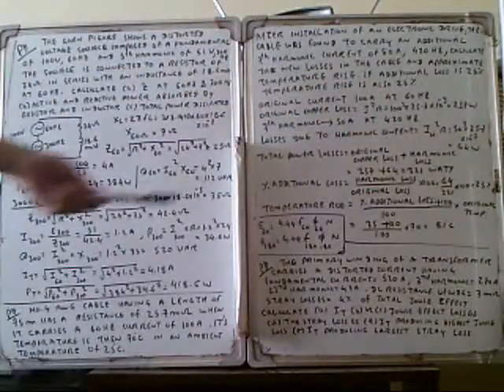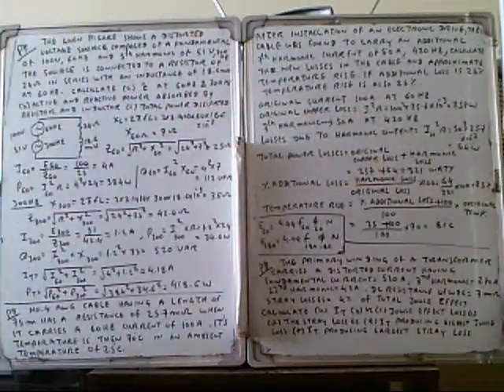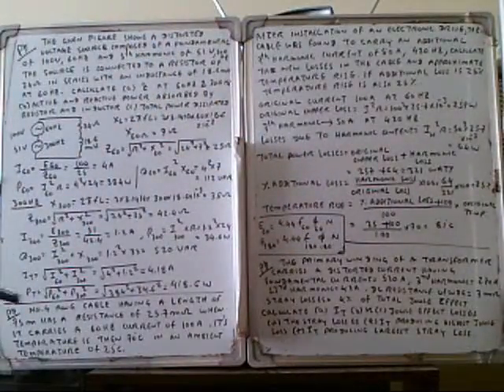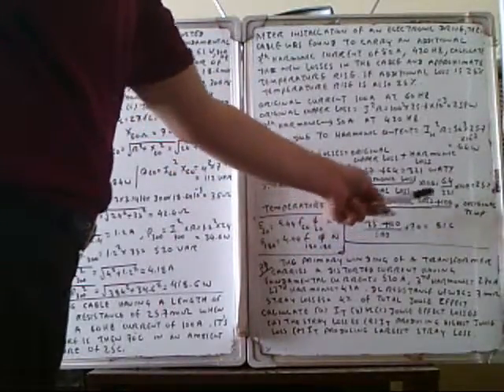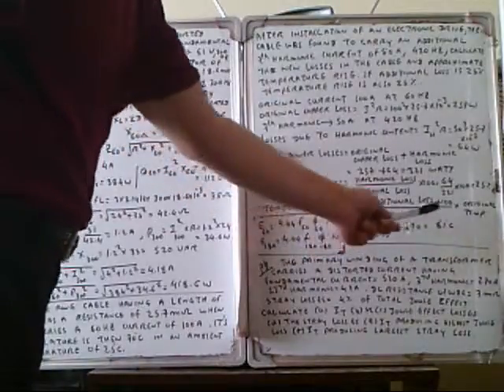Percentage additional loss: harmonic loss divided by original loss times 100. Harmonic loss is 64, original loss is 257. 64 divided by 257 times 100 equals 25%. Temperature rise formula is: percentage additional loss plus 100 divided by 100 times original temperature. Original temperature is 70 degrees centigrade. 25 plus 100 divided by 100 times 70 equals 87.5 degrees centigrade. This is how we calculate temperature rise due to additional losses.